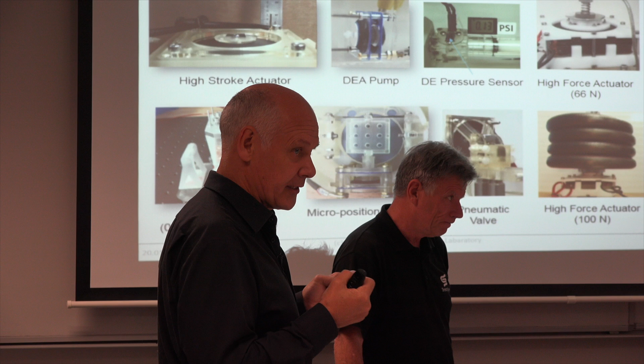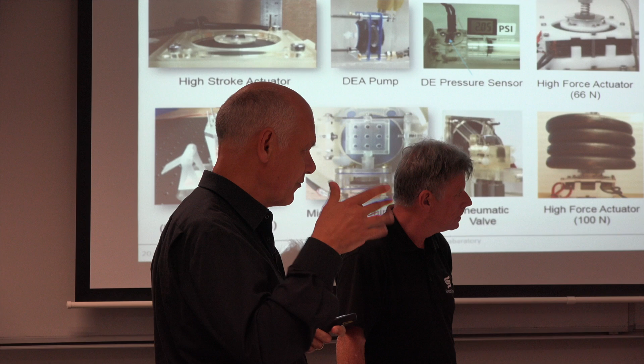You had a question? So I wanted to ask the same question about how reliable they are under high cycles, because it's based on an austenite-martensite transformation, so detwinning and reversibility. So, what, as you said. Yeah. A lot of this depends on the design, the mechanical loading that I just mentioned, but also surface properties. The mechanism of failure is cracks, right? So if you have a very rough surface and you start under tensile loading, then you have these cracks propagating quite quickly, so you have to make sure you have very good surface properties. You have to look at the alloys. There are special ways of coming up with very low inclusion alloys where there are no additional phases where microcracks generate and propagate, and all this has to be taken into consideration.